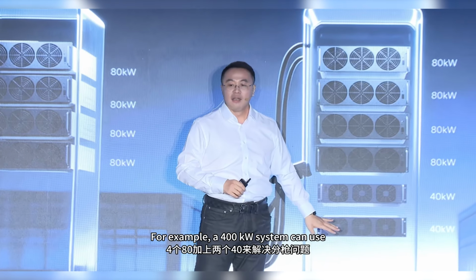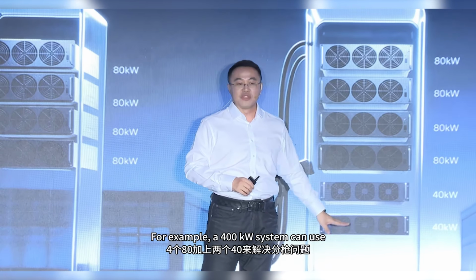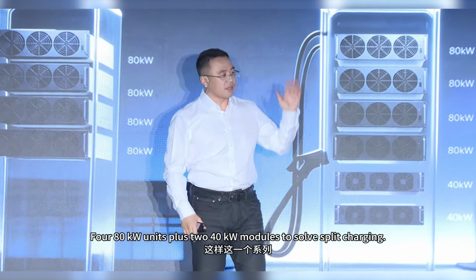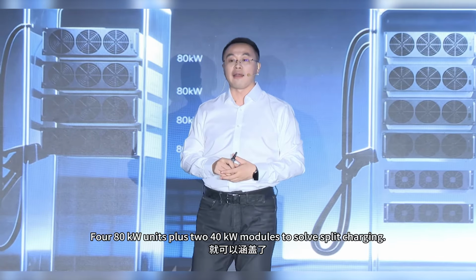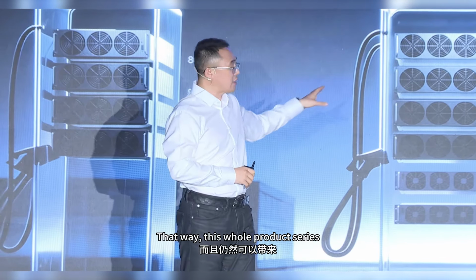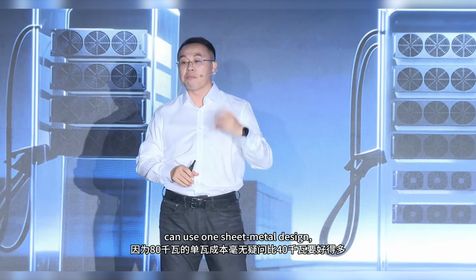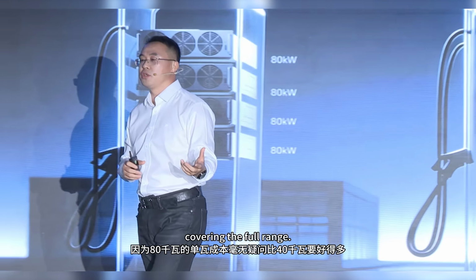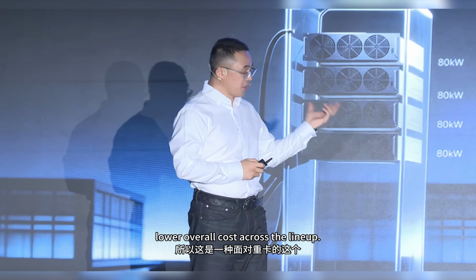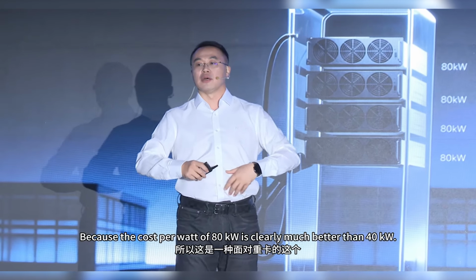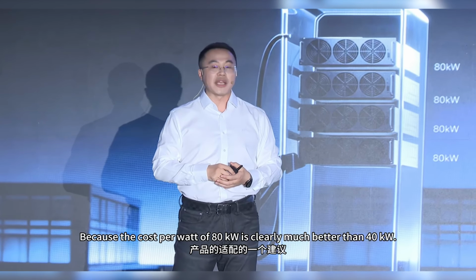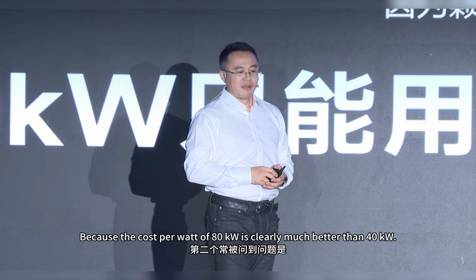For example, a 400 kilowatt system can use four 80 kilowatt units plus two 40 kilowatt modules to solve split charging. That way, this whole product series can use one sheet metal design covering the full range, and it can still deliver lower overall cost across the lineup, because the cost per watt of 80 kilowatts is clearly much better than 40 kilowatts.